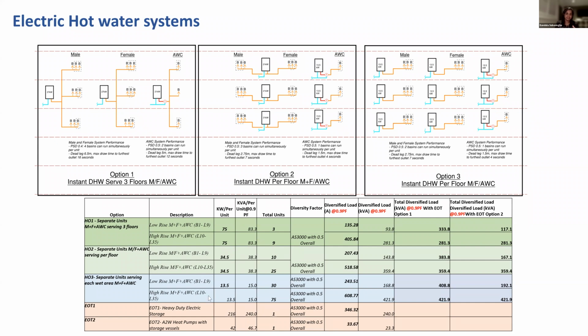As you can see in this table, the kilowatt per unit for heat pumps is much less than the others. The only drawback is you have a large heat pump somewhere in the basement, and then you have to run hot water throughout the building to reach each level. That dead leg means you have to wait a couple of minutes or a few seconds after opening the tap to actually get hot water, which isn't ideal for some installations.